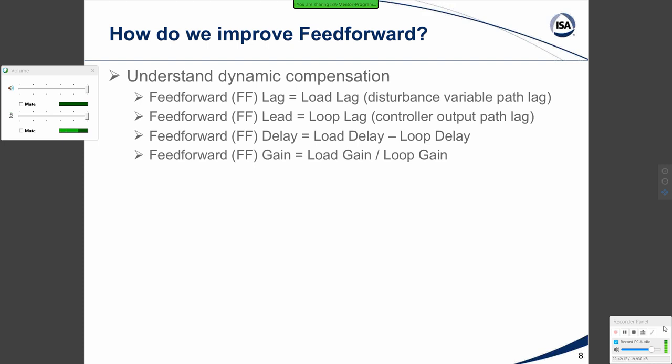In other words, wherever the biggest lag is to get that correction into the process at the same point as the disturbance, the biggest lag there. And maybe it's the secondary lag in the controller. If there's not much of a secondary lag in the process, it could be the valve. And that's actually what we saw in a big application of feed-forward control that we'll get into for header pressure control. The lead was really set based on the lag in the control valve. And even though we had made these control valves much more responsive, it still was important to set that lead.